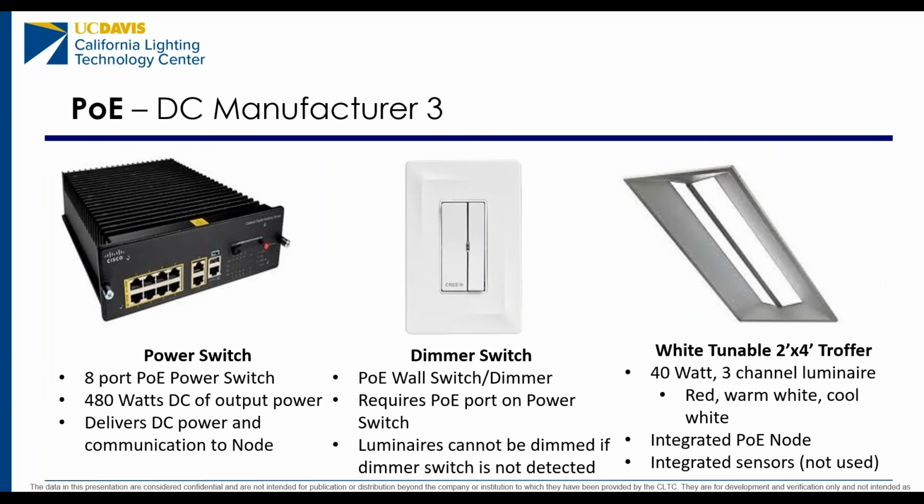Second PoE system we looked at, which we'll refer to as DC Manufacturer 3. Similar to the first, we used the exact same power switch. In fact, for most PoE systems that we could find, the manufacturer suggested using this power switch. So we used the same power switch, and then as a load on the power switch, we bought 8 of these 40-watt white tunable LED luminaires.